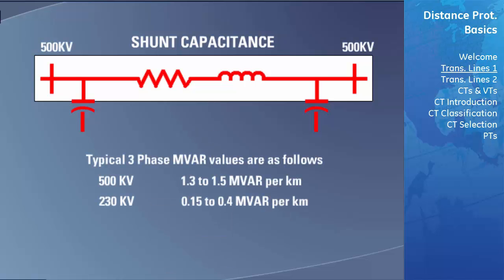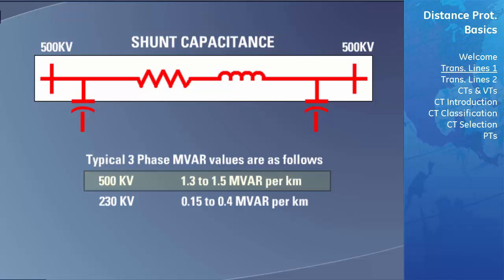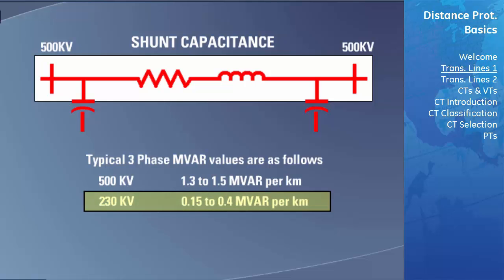Typical three-phase megavar values are 1.3 to 1.5 megavars per kilometer for 500 kilovolt lines and 0.15 to 0.4 megavars per kilometer for 230 kilovolt lines. Caution needs to be taken when transmission lines are used with high voltage potentials. Due to the Ferranti effect, the shunt capacitance on the line can become so large that the voltage on the far end of the line can rise higher than the normal line potential.